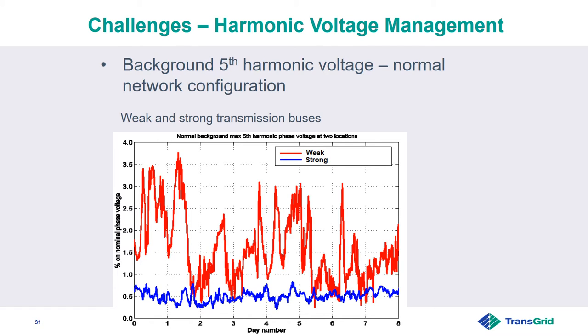These are measured fifth harmonic voltages over a week at the weak and strong network location we looked at in the earlier slide. It can be clearly seen here that the harmonic voltage at the weak transmission bus is significantly higher than the other. These measurements at the weak location demonstrate two key aspects. First, these harmonic voltages result from amplification of remote harmonic voltages, not from any harmonic source connected at this location. Second, the level of fluctuations in the harmonic voltage at this location indicates the sensitivity of harmonic impedance at this location to various events occurring in the network, such as switching in and out of shunt reactive plant.